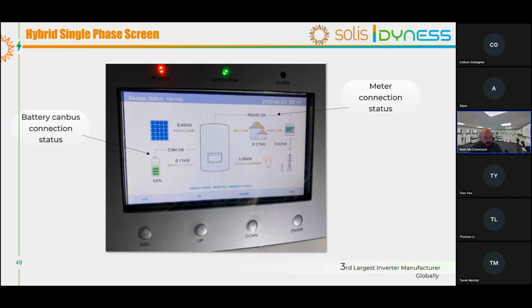You would then see the SOC of the battery, so that's another indicator to make sure that you're actually getting the correct information from the battery. You would then see how much power is going into it or out of it, based on the present flow of the system. That's also real-time information, so it's not like the 5-minute delay I discussed with Solis Cloud. That's actually on the screen, so you'll be able to read what's happening. The bottom right-hand side shows the backup port, where the light bulb is. If the customer has loads connected to the backup port, you would see what's actually running through the inverter to the backup port, and if they don't have it, then it'll just have 0, of course. You also have the PV side in the top left, which will show you how much PV you're getting into the inverter. And then on the top right, there's a few things we need to look at.